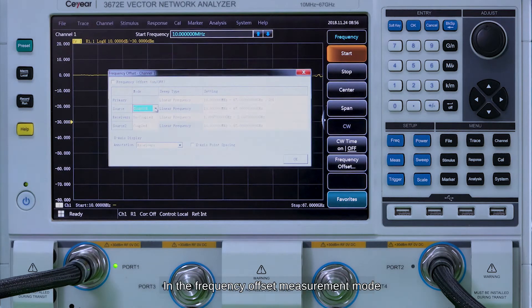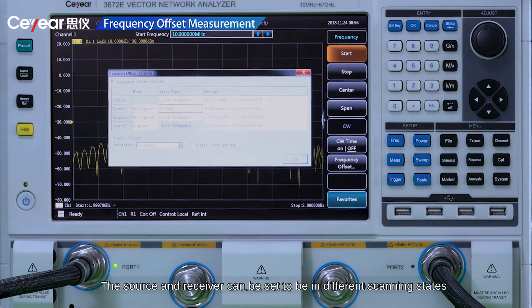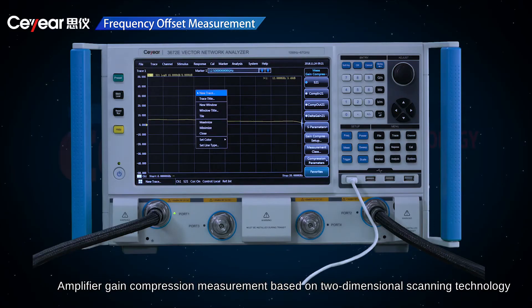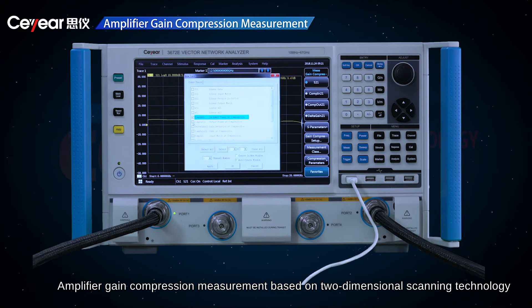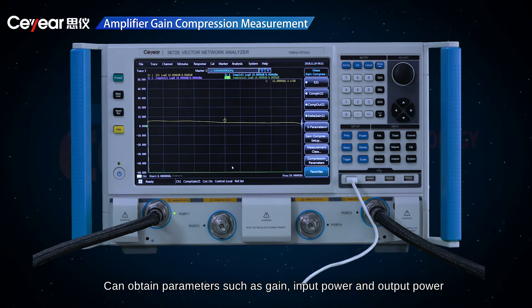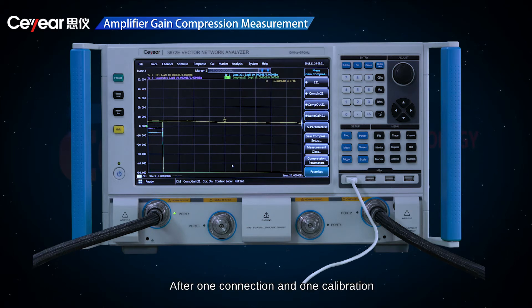In the frequency offset measurement mode, the source and receiver can be set to be in different scanning states. Amplifier gain compression measurement based on two-dimensional scanning technology can obtain parameters such as gain, input power, and output power of the full-band compression point after one connection and one calibration.